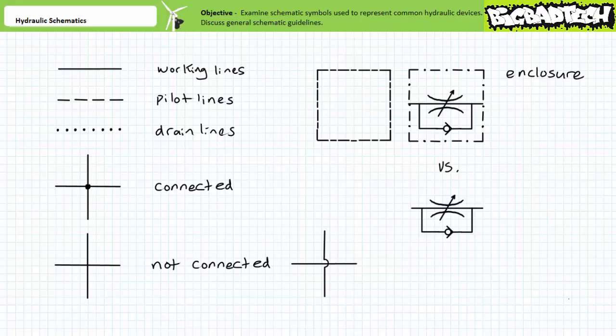Another good example of an enclosure being put to use is a single valve body containing two or more devices. Consider a variable flow control valve with an integrated check valve bypass. Lacking the enclosure symbol could mean that this is composed of two independent devices, a variable flow control valve and a separate check valve that need to be connected together in the proper orientation of function. The enclosure symbol around these two devices makes it painfully obvious that this is really just one device inside the same valve body. Manufacturers may or may not go to the trouble of drawing enclosure symbols around integrated devices.